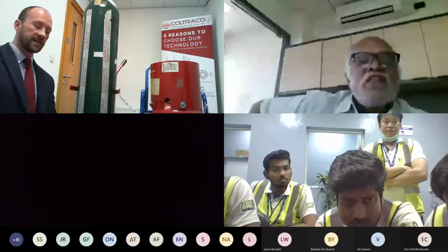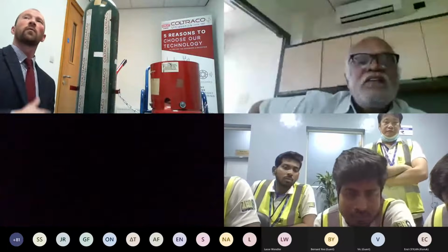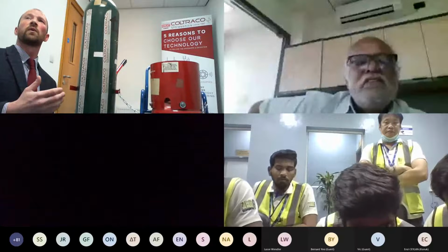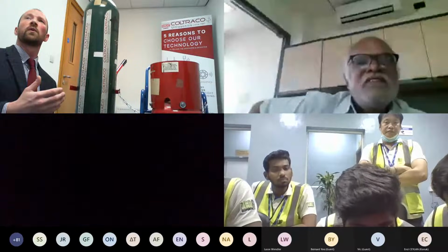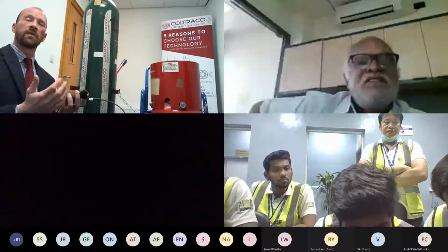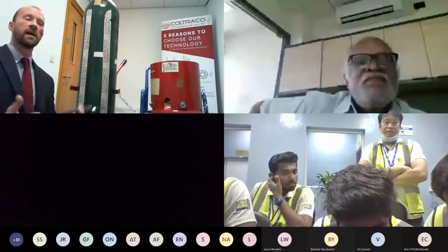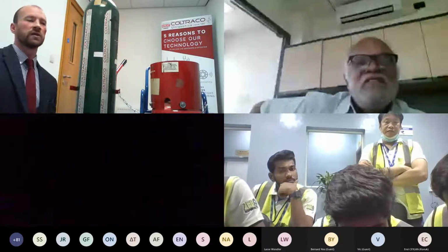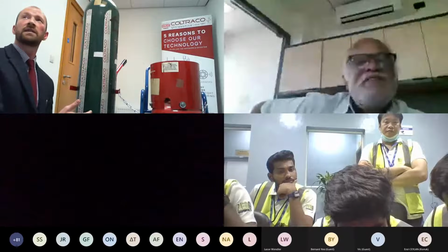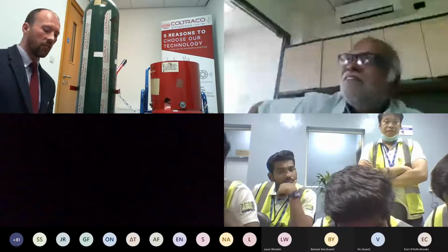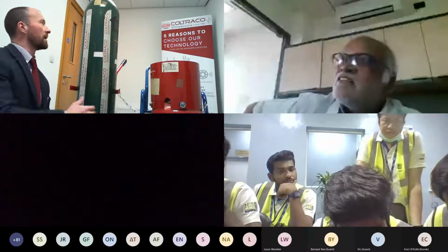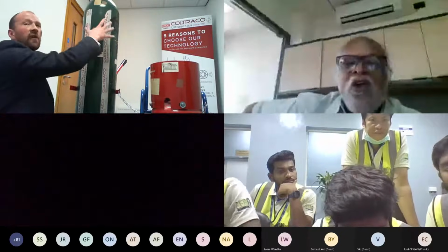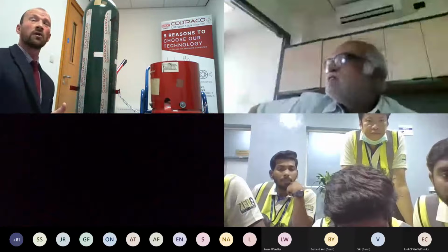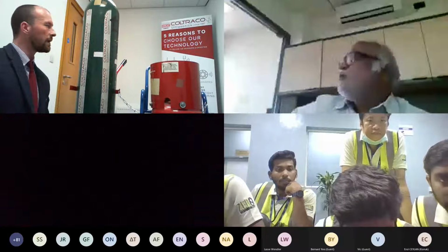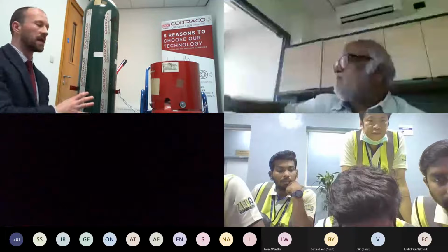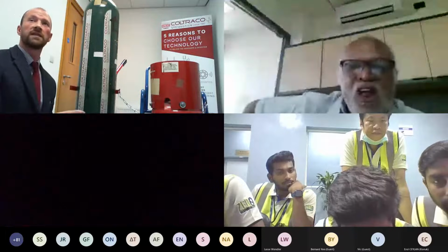So Cal1 is the default on this, which is again in a similar situation where you've got quite a large drop off. However, I wanted to explain that with Cal2, the difference is when the drop off is much larger. Cal3 is used for challenging cylinders which have been perhaps rusty or a little bit older, and also cylinders where the difference between the sort of high readings and the low readings isn't very large. That's where we use Cal3. So just wanted to quickly recap on that before we move to the FM200 cylinder.